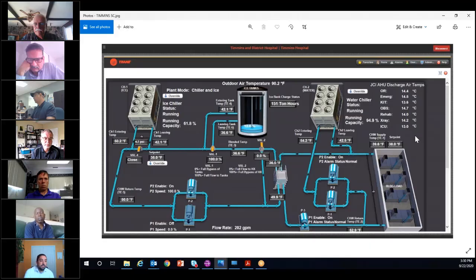And we can do critical discharge temperature reset based on any of these. So if, for example, your OR air handler leaving temperature is creeping up, we may do a system reset on the whole system to make slightly colder chilled water to make sure that we are maintaining required temperature and humidities in some of those critical spaces.